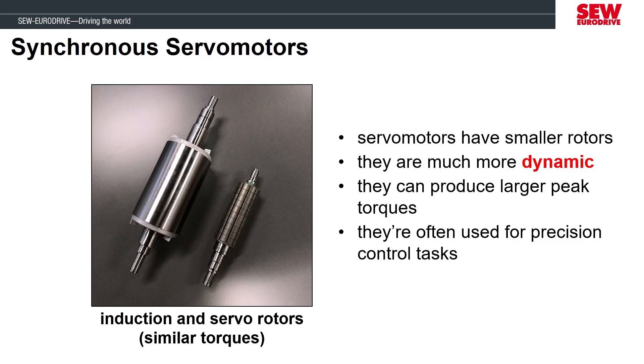This doesn't mean the servo motor is always better than an induction motor. Servo motors aren't suited for every application, especially those with high inertia. Since the rotor shaft mass of a servo is much smaller, it can be difficult for the VFD to accurately control it if the application has a load inertia that is a lot higher than the rotor inertia. These are points that must be discussed in the project planning phase for an application to determine which motor type would be better suited.